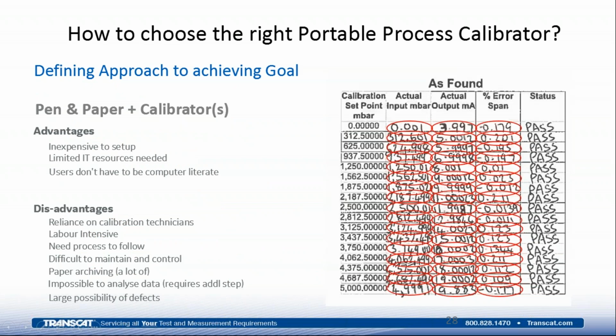So pen and paper, there are advantages and disadvantages of each one of these approaches. Obviously with pen and paper, it's inexpensive to set up. There's not a lot of setup. You don't need any IT resources. Users don't have to be computer literate, don't even need a laptop per se necessarily. Just writing down values off a calibrator onto a calibration sheet. Disadvantages would be reliance on calibration technicians. It's somewhat labor intensive or more labor intensive. There's a need to have a rigid or defined process to follow. Slightly more difficult to maintain and control.